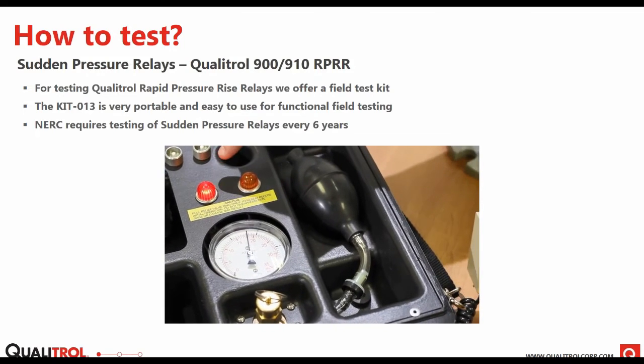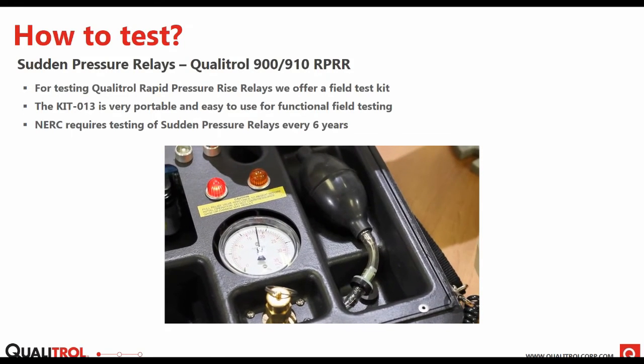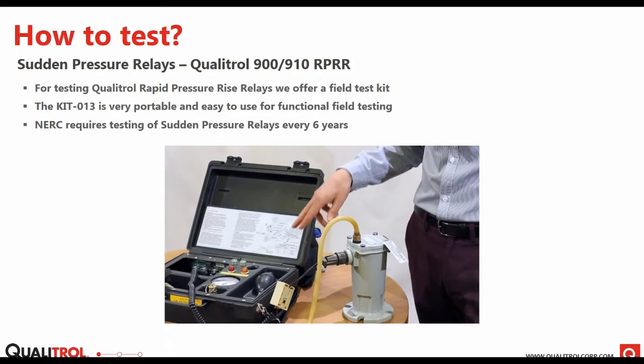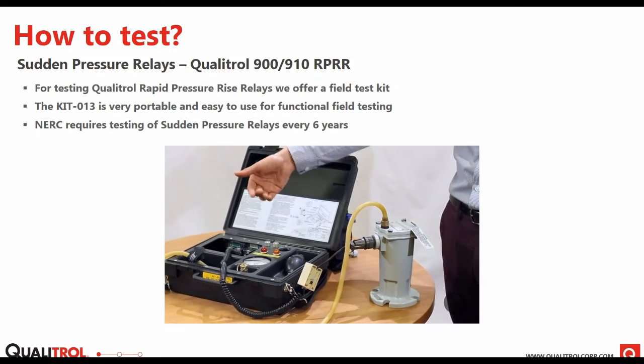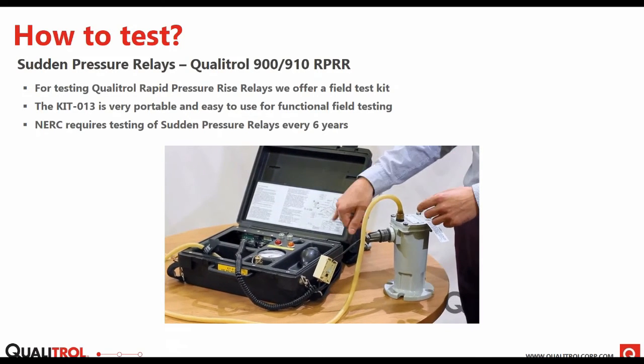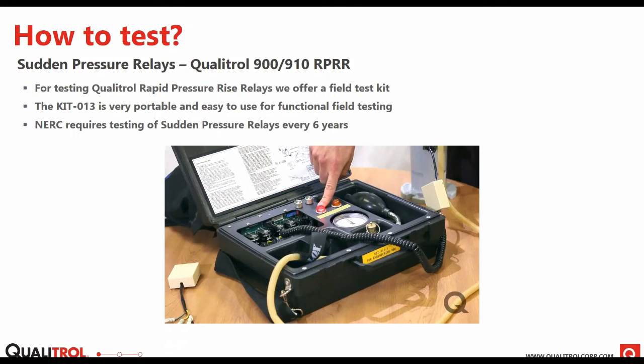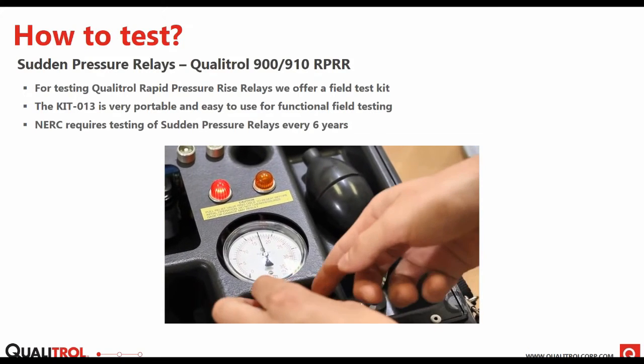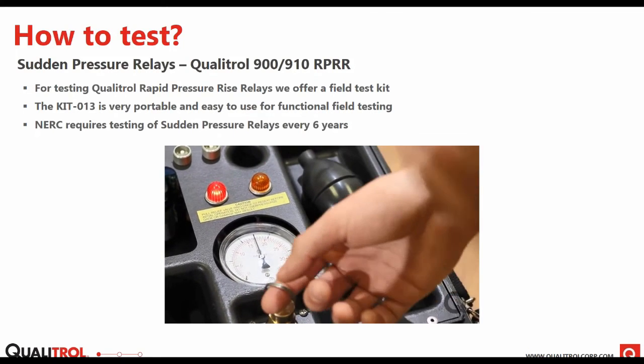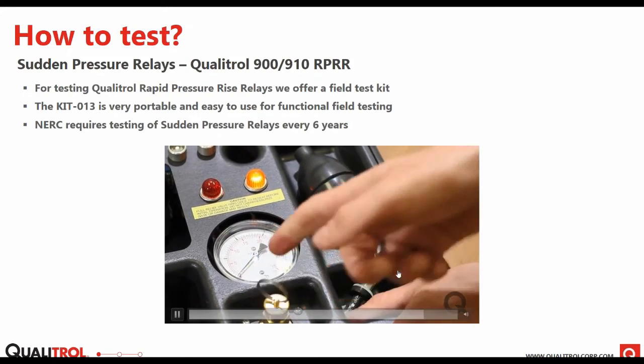If you increase pressure on the top of the system, it will equal out, and it will be back in a normal state. So what we do with the kit is we apply pressure on the top, let the bellows level out and go back to a normal state, and then we quickly relieve the pressure from the top, which will simulate a sudden pressure on the bottom, driving the bellows into the switch and actuating that switch. You can see that here in the video.